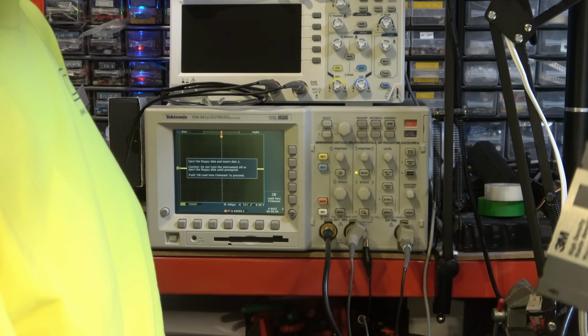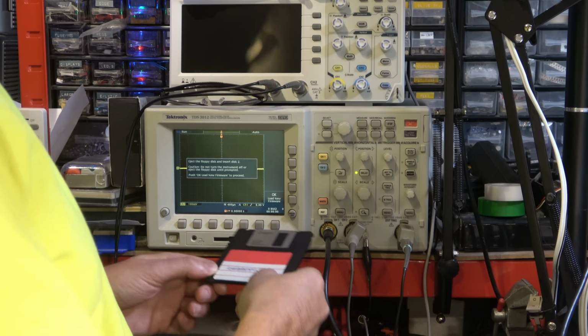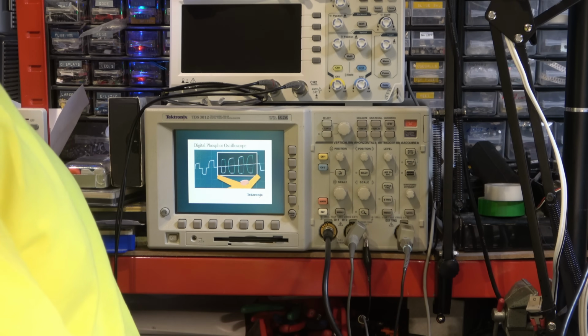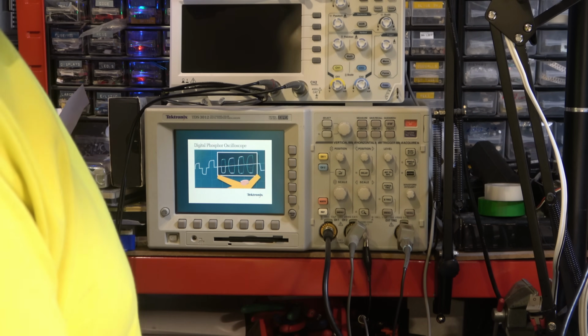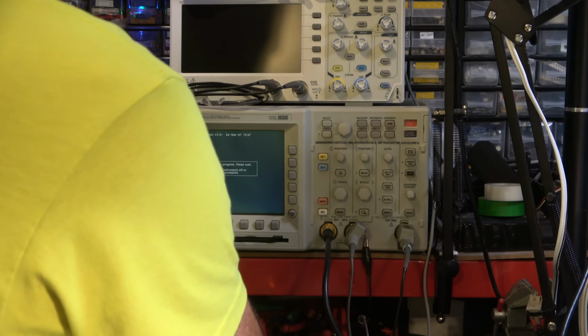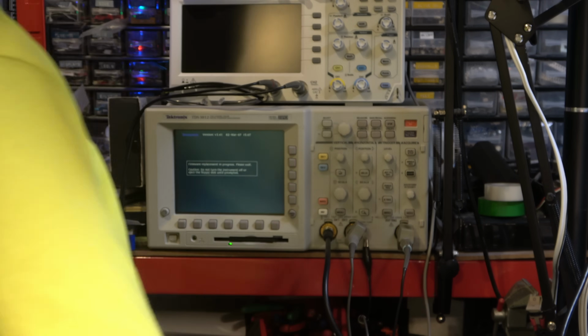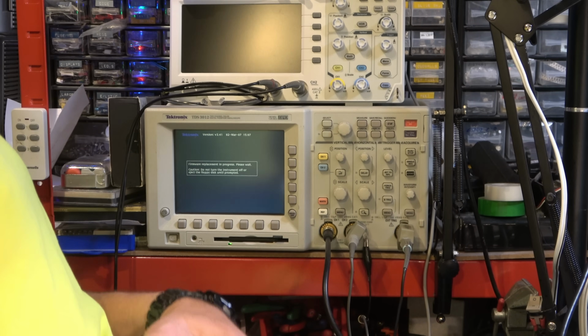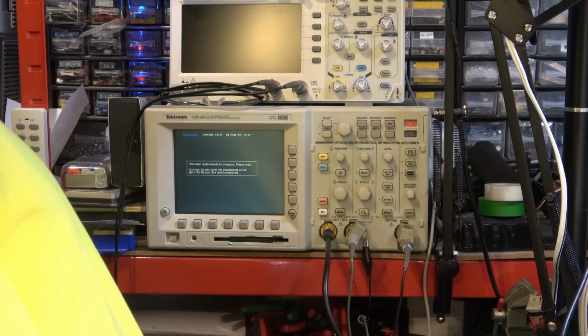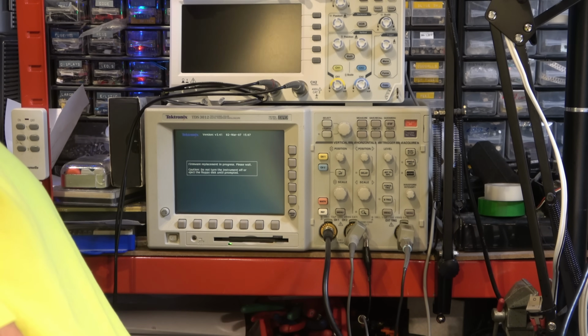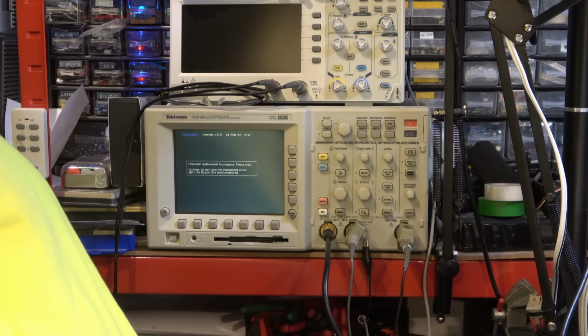Right, so we're working on the assumption that I messed up on that disk or it was corrupted, one or the other. What does the instructions say will happen after 2? Because it's done a reboot. Oh, firmware replacement in progress. Please wait. Do not switch off. Yes. Instrument may or may not reboot itself once disk 2 has been loaded. In any event, wait until your prompt is input.